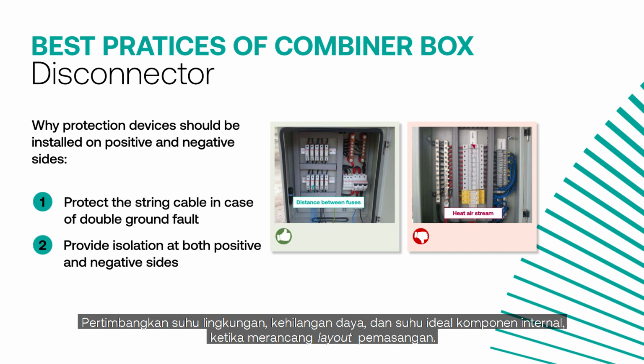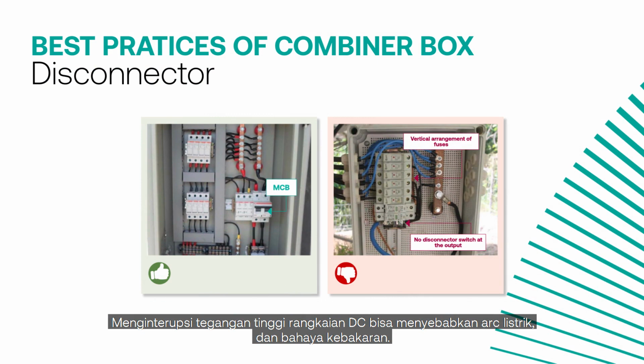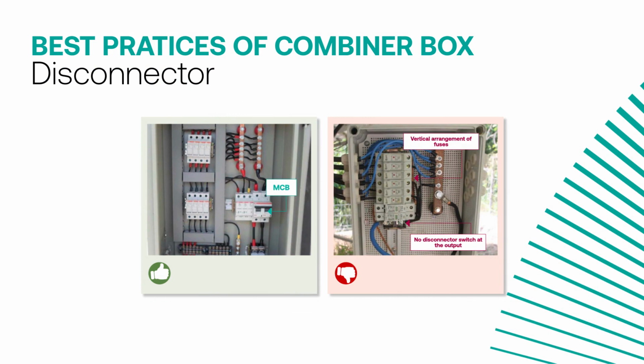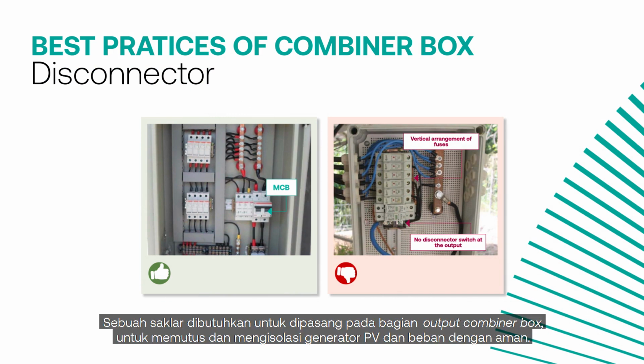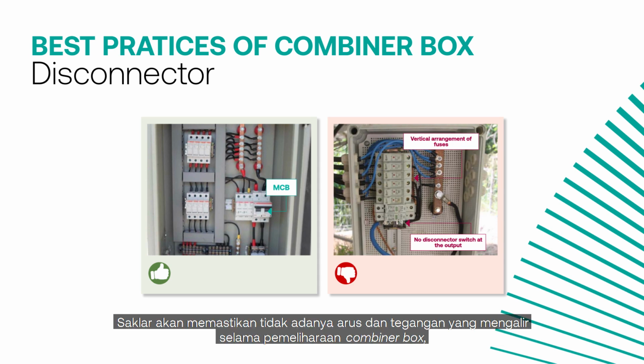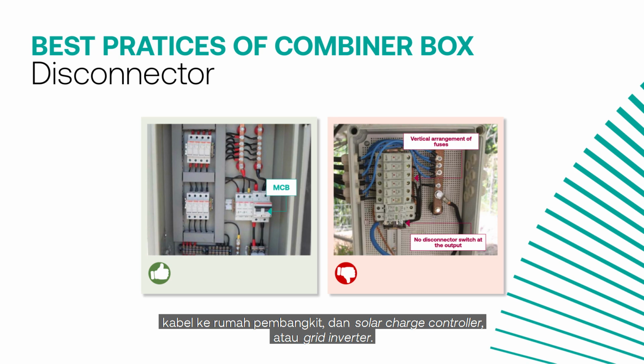Consider ambient temperature, power losses, and ideal temperature of the internal components when designing the layout of the installation. Interrupting a relatively high voltage DC circuit may cause an electric arc and possibly lead to fire hazards. A switch is required at the output of the combiner box in order to safely disconnect or isolate the PV generator and load. The switch will ensure the absence of flowing current and voltage during service and maintenance on the combiner box, wiring to the power house, and solar charge controller or grid inverter.